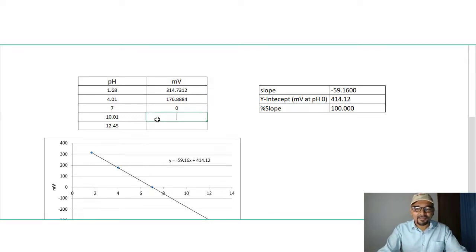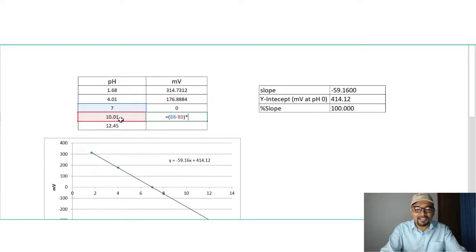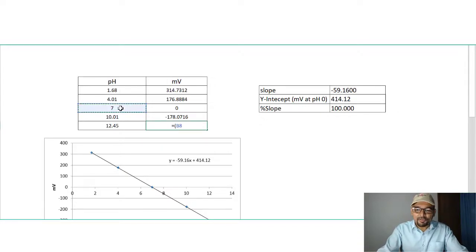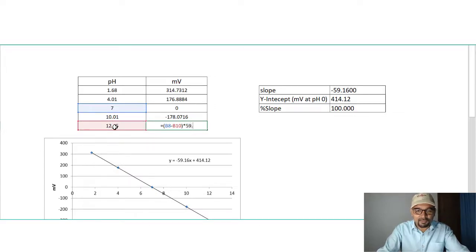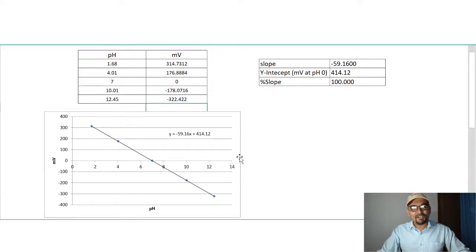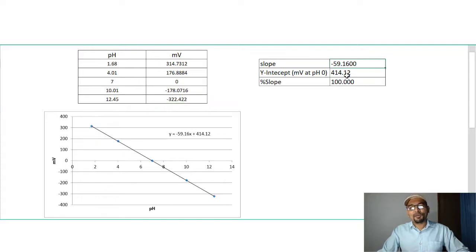For pH 10.01, after calculating the difference and multiplying by 59.16, the ideal potential is minus 178 millivolts. For pH 12.45, the potential is minus 322 millivolts. You can see a beautiful linear line in the table. The slope is minus 59.16, and the y-intercept — the millivolt at pH 0 — is 414 millivolts.